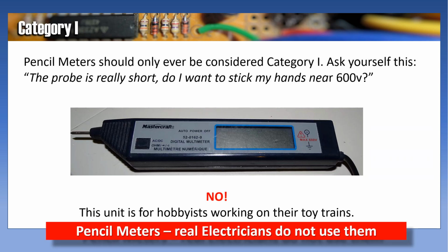Pencil meters should only ever be considered Category 1. I mean, even if it says Category 2, still think of it as Category 1. Ask yourself this. That probe is really short. Do I want to stick my hands or fingers near 600 volts like it's rated? No. This unit again is for hobbyists working on their toy trains. Pencil meters, real electricians do not use them.